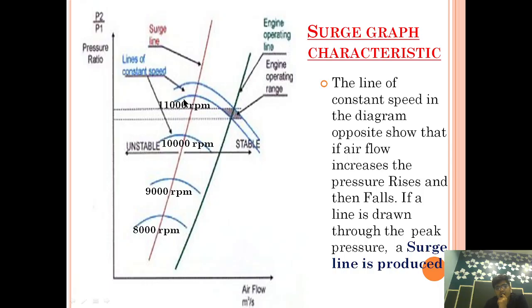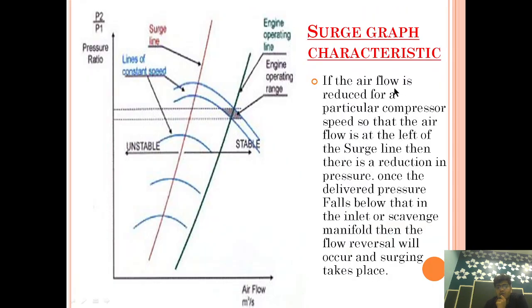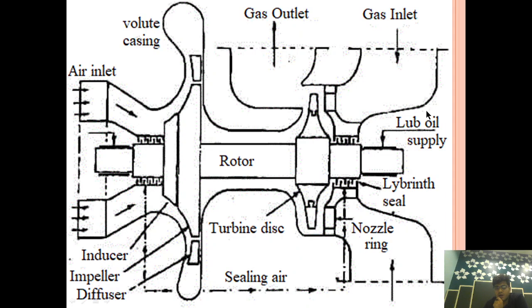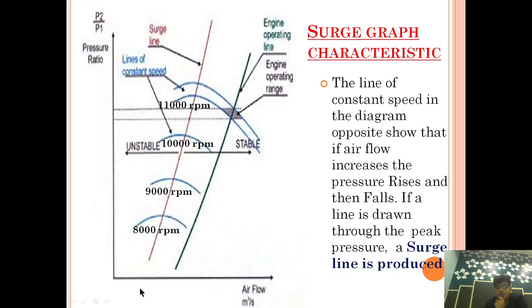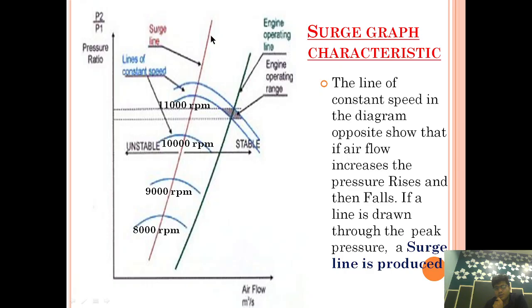As you can see, after the surge line the pressure is dropping. So now you know what the surge line is. If anyone asks, you can say: a line drawn based on the peak of each constant speed line is called the surge line. Now if airflow is reduced for a particular compressor speed, let me explain what happens in a normal scenario — air is flowing in and coming out, entering at 1 bar and exiting at 4 bar, giving us a peak point from which we draw the surge line.